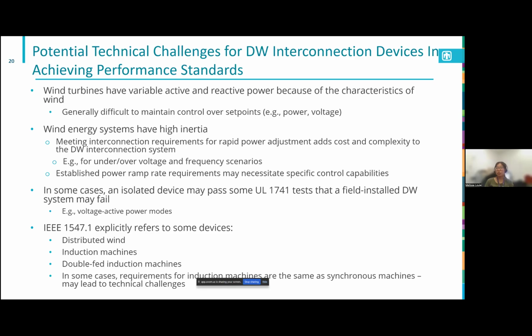From a system integration standpoint, there is the possibility that isolated DER interconnection devices may pass UL 1741 tests but not guarantee that the fielded system with that device installed would pass.